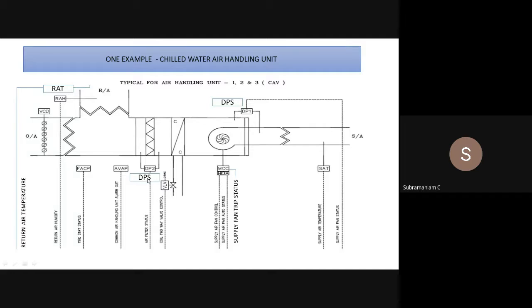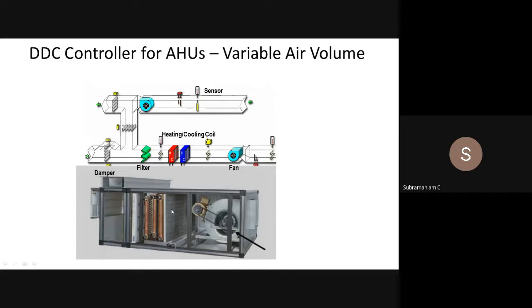Motorized valve. Now, whether my filter is clean or dirty, I can put a differential pressure switch here and find out. If the filter is clean, the pressure drop will be less. If the filter is dirty, the pressure drop will be more, because there is resistance to the airflow. Then I can measure that and say whether the filter is dirty or clean, whether fire alarm is there, and operate the outside air damper, and return air humidity. So all these are field devices. They will come to the DDC controller. Like this, if you take an AHU, these are the things that you can have.